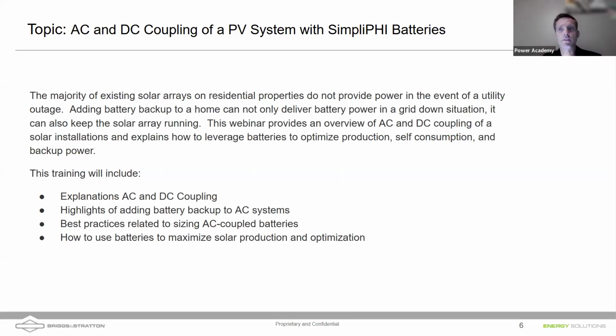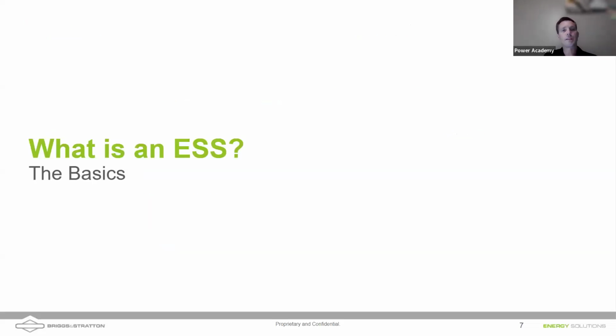And that battery can either be DC coupled to the solar array or AC coupled. One of the focuses of this talk is to understand the difference between the two. We'll talk about some of the highlights of adding battery backup to AC systems. We'll talk about some best practices related to sizing AC systems to batteries. You want to make sure you have enough available charging capacity of the battery to take the full power of the array in a grid down situation. And we'll also talk about how to use batteries to maximize solar production and optimization.